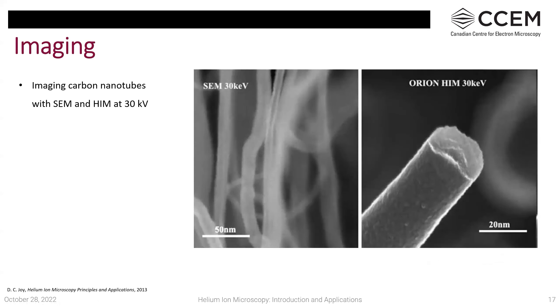Another comparison between SEM and HIM: to the left is a scanning electron micrograph at 30 kV, and to the right is a HIM micrograph of carbon nanotubes. At higher SEM energies, the beam passes through the nanotube and most surface features are lost. With the HIM, you can see superb surface details, texture, and roughness.